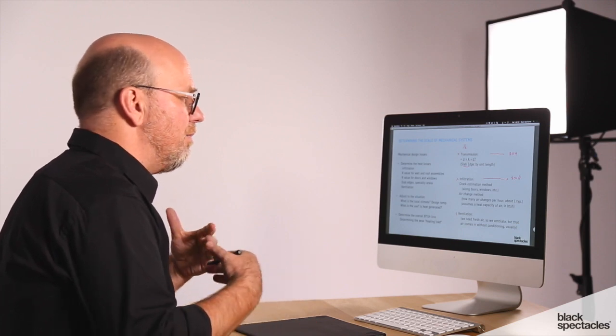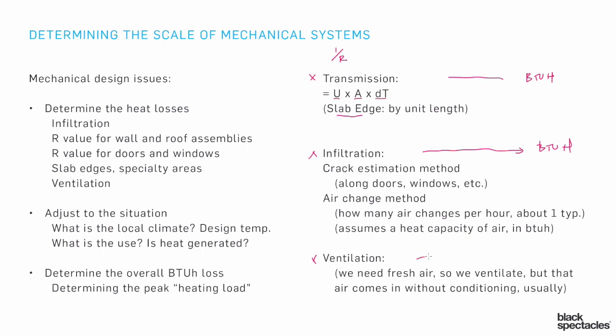We now have a couple of those numbers. We don't always include ventilation — it depends on the situation — but the more we know we'll need fresh air that won't be preconditioned, the more we need to account for that heat loss, which also gives us some BTUH. We add all three individual numbers together to understand our total heat loss per hour — that tells us how much heat the system needs to produce.